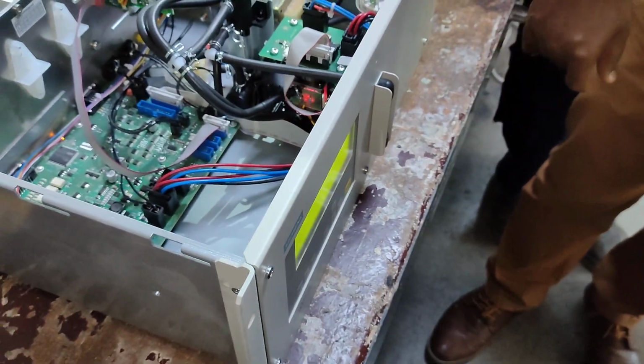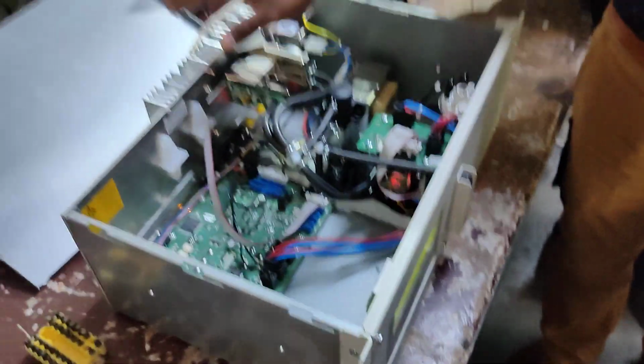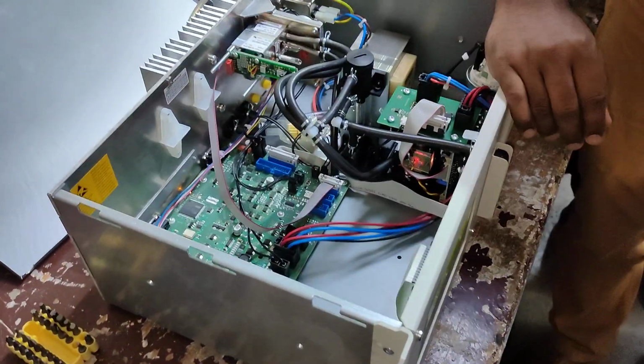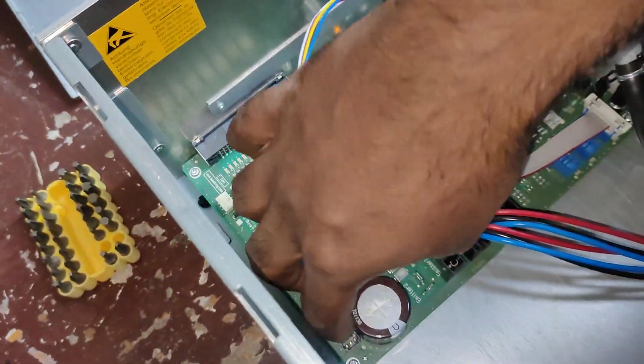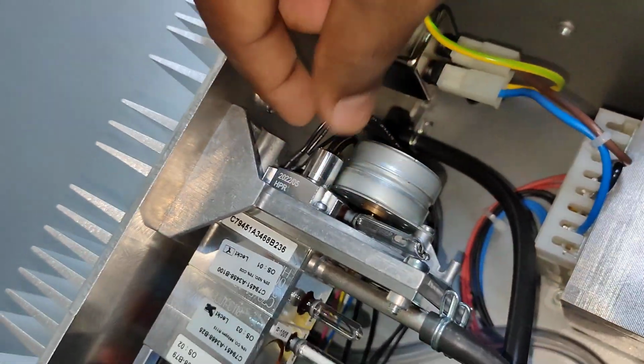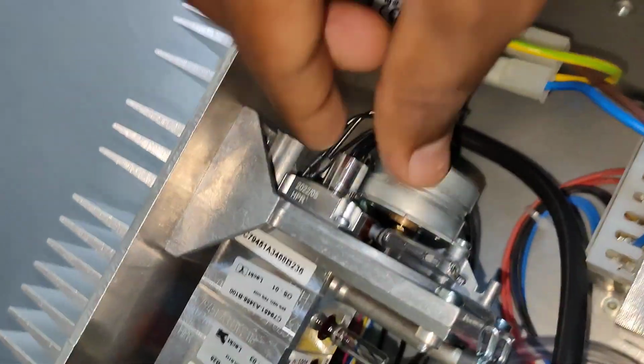There are some parameters. With those parameters, you can verify whether the detector is working or not. I will give that parameter. This is the cable for the chopper motor. It is powered by the motherboard and comes directly to the chopper motor. The individual chopper motor you can replace. Your IR source you can replace. We have 2 screws. You remove these and you can replace the IR source.